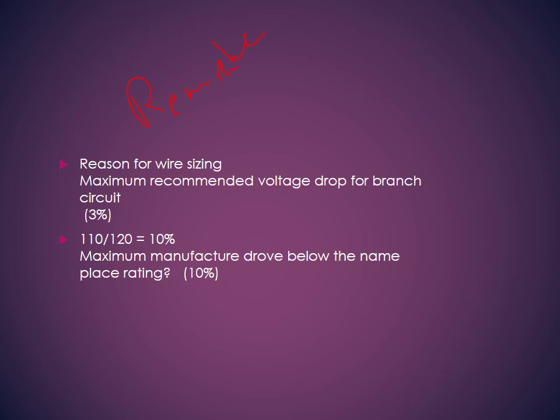Remember that the maximum recommended voltage drop for a branch from the main voltage source is 3%, and when we look at the nameplate, we cannot drop more than 10%. So for any equipment, whether it be an AC, a furnace, or so on, you cannot have more than a 10% drop. And if you have, for example, a very long run of wire and you drop more than 10%, you might want to increase the wire gauge, like from 14, you might go up to 12 if you have to.